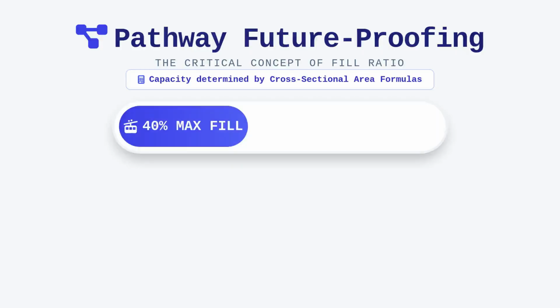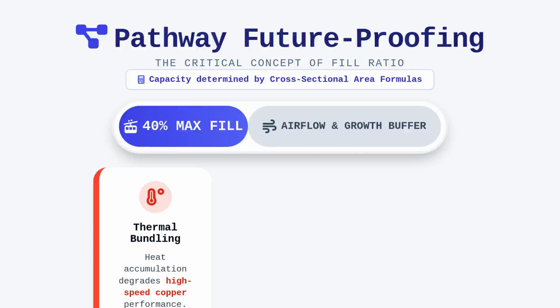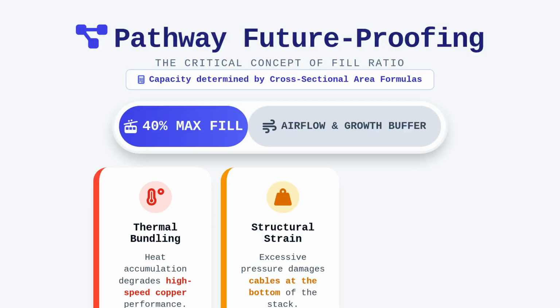Pathways must also account for future-proofing, which brings us to the crucial concept of the fill ratio. We utilize specific cross-sectional area formulas to determine the capacity of conduits, cable trays, and raceways, with a standard industry limit often enforced at 40% total capacity. This might seem inefficient to a casual observer, but it is a critical safety margin designed to prevent thermal bundling and structural strain on the cables at the bottom of a stack.